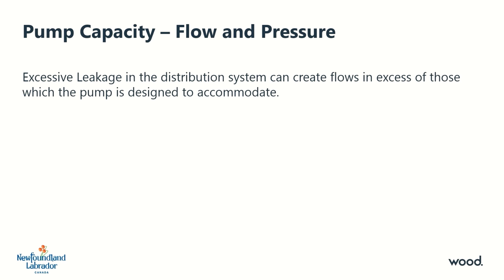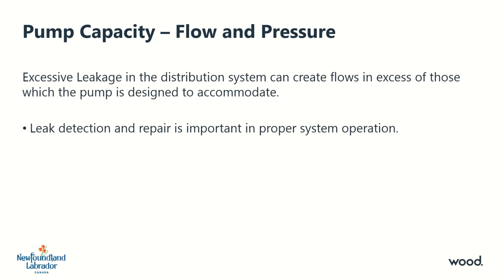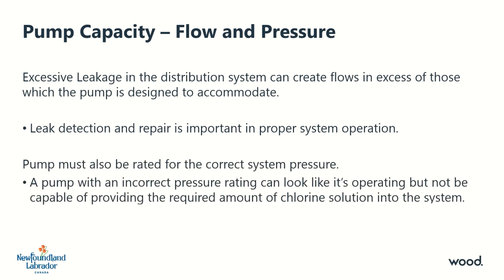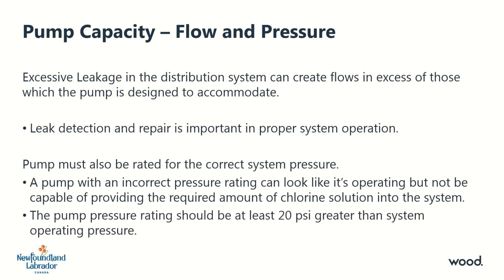Pump capacities can sometimes be compromised due to excessive leakage in the distribution systems, creating flows that are in excess of what the chlorination system was designed for. Leak detection and repair is important in proper system operation. Also, if the pump being used is not rated for the correct system pressure, it may appear to be operating correctly, but may not be capable of providing the required amount of chlorine solution into the system. The metering pump pressure rating should be at least 20 psi greater than the distribution system operating pressure.